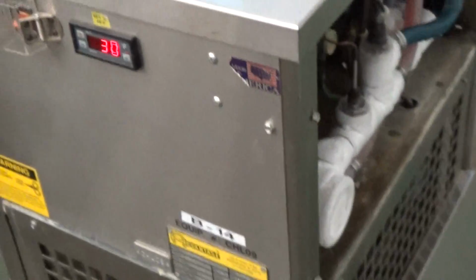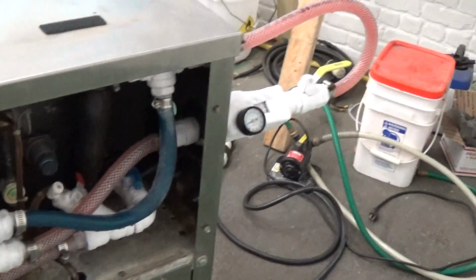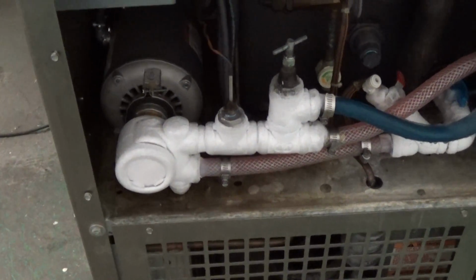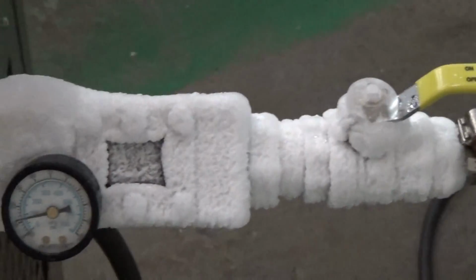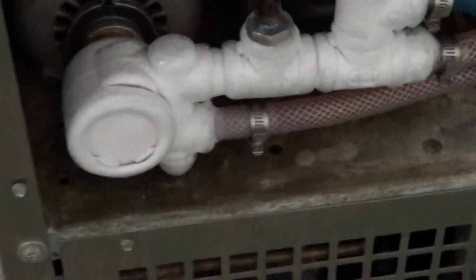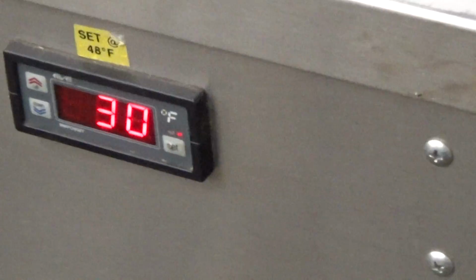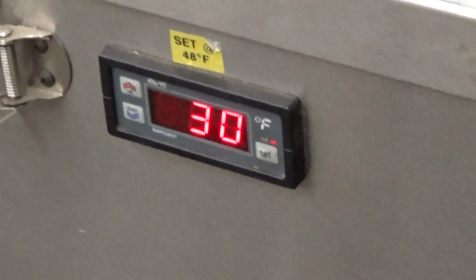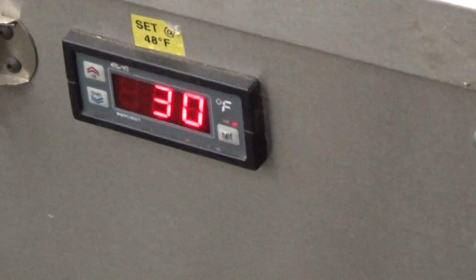So as mentioned, the pump runs the whole time. The compressor just turned on. And the reason we're going to start kind of backwards here is because I didn't want to change the temperature, because I just wanted to show that the uninsulated components here have frost all over them. Again, just adding to our claim that it's been running for several days at 30 Fahrenheit set point. So what we're going to do after this reaches our set point is raise it back up to like 45 or so, let it get up to temperature, then show it chill all the way down to its 30 or 28 F. But when we do that, it's going to lose all this frost.